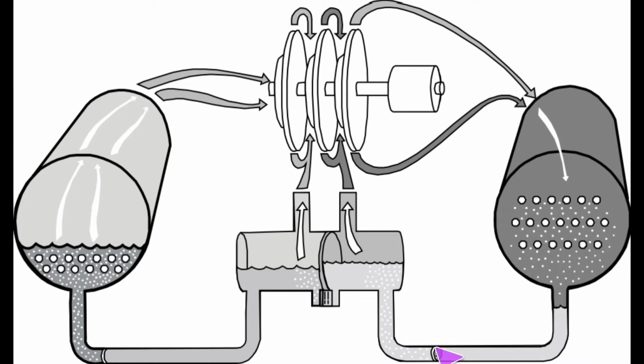This will usually have a stub out to where it'll actually look very much like this. It'll come out the bottom of the condenser as part of the liquid, and then it'll flash, and then this will come up into the economizer, and usually they'll be insulated from this point on. And like I said, you'll see these are, I think, like a 4 to 6 bolt flange depending on the size of the machine. Other than that, it's all the same, right? We come through the evaporator, guide vanes, compressors, all of it's the same. This is what's extra. Now let's cycle over and we'll take a look at the graphic of this economizer.